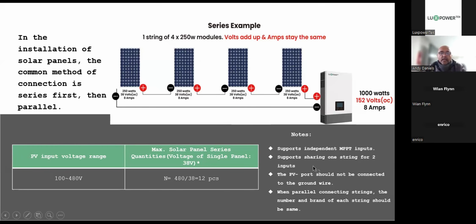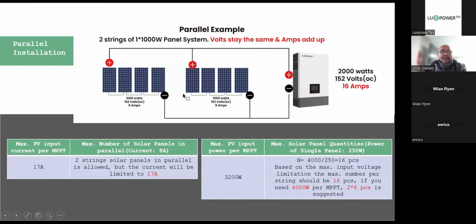Okay. What happens when we go to parallel strings? You can see here, in this instance, you've got a parallel string there, and a series string there. And then what they've done is they've paralleled the 2 positives and they've paralleled the 2 negatives. Then they bring it into the inverter. Oh, sorry, this is wrong here. It should be 4,000, but your limitation there will still be 17 amps.